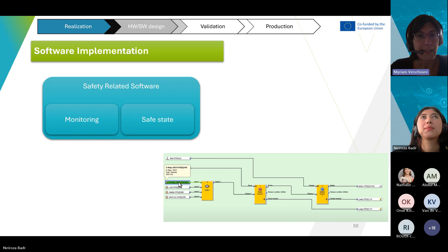On the other hand, in software, two very important items are configuration and parameterization. You could be doing a very good job in software implementation, but you could also be doing a very bad job by having a wrong configuration or parameterization, resulting in risks you want to avoid. This means that for software implementation you need a proper process for software configuration management. Second, parameterization should only be allowed to be performed by trained personnel, always documented, and always used with a verified tool. These are very important.